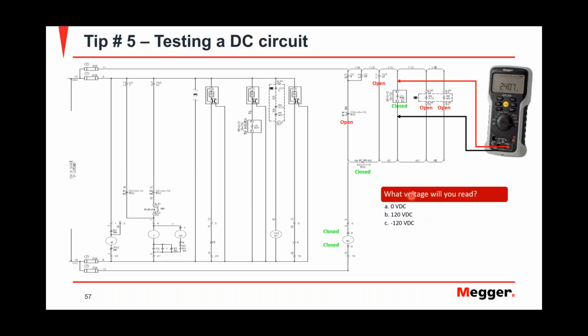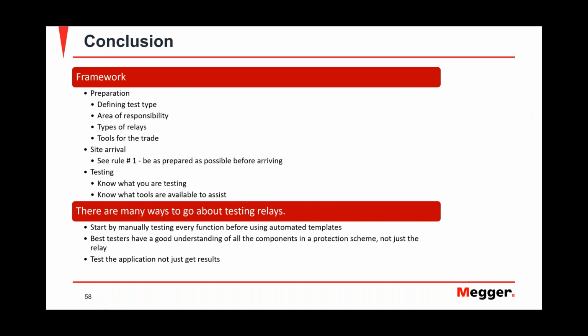So now at that same moment, let's say you have another meter, but now this time you're looking at your closing contact. What would you see across it the moment that it closed? And the answer is 0 volts, because now your voltage drop is here, and this pretty much becomes a short circuit. So you should see 0 volts in there. If you don't have this understanding and you want to troubleshoot DC circuits, it's going to be a problem.